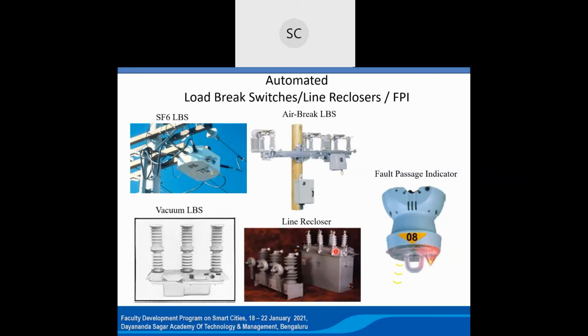So in the third shot, the fault is still there. So what happens? Permanently it will trip, and that information goes to control centers, stating the indication that it is a permanent fault on that recloser. By this time, we are using various sectionalizers within that radial network, so that whatever time delays are there are maintained.